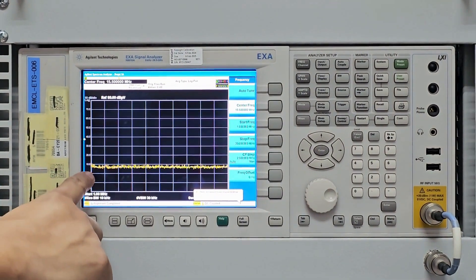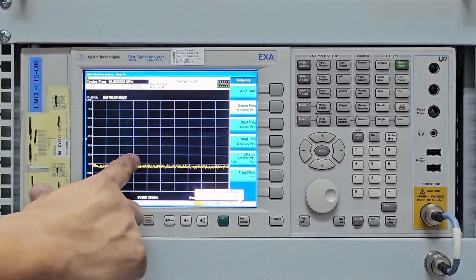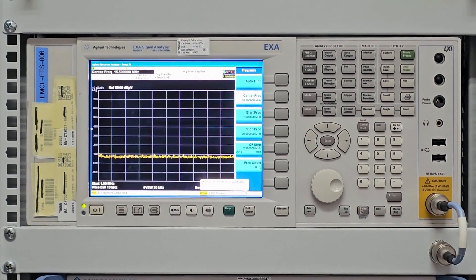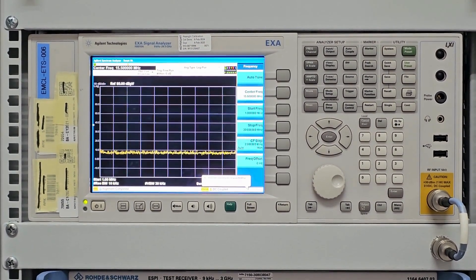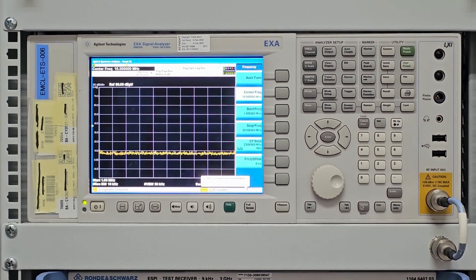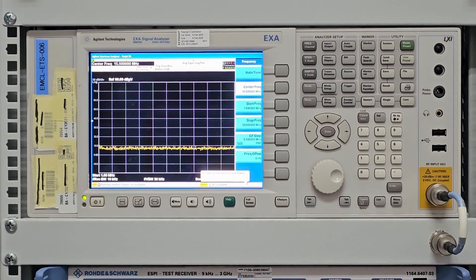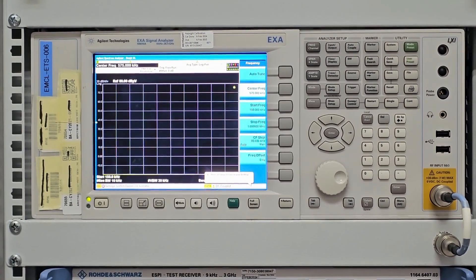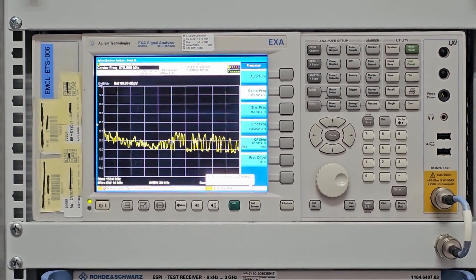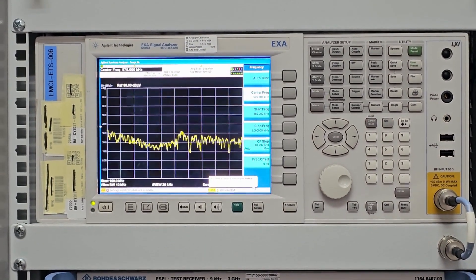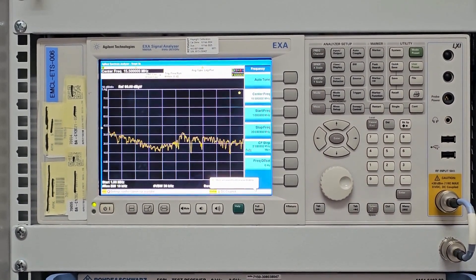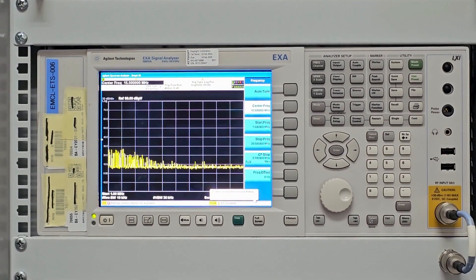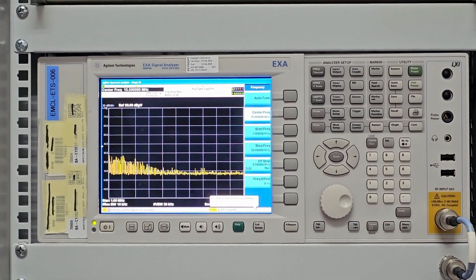On the spectrum analyzer view, you can see the noise floor when the LISN has no DUT connected. Now we are ready to connect the DUT to the LISN. After connecting the DUT, I will execute the test and measurement instruction for conducted emission. You can see that the system is doing a peak search from 150 kHz all the way to 30 MHz. This peak search is performed by the spectrum analyzer, measuring across the full range.